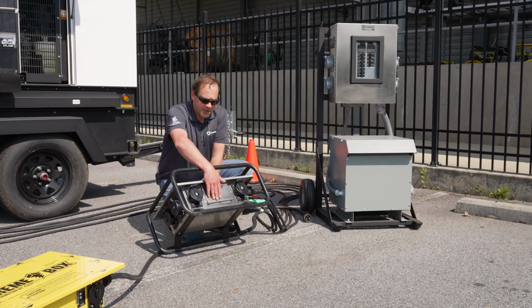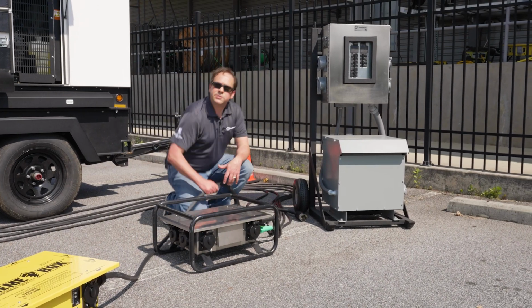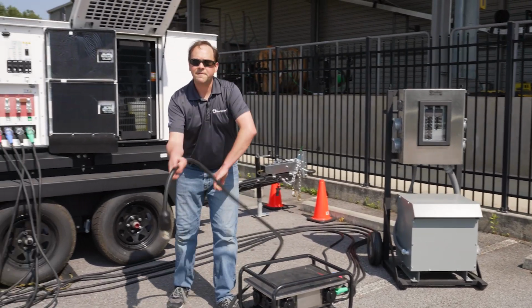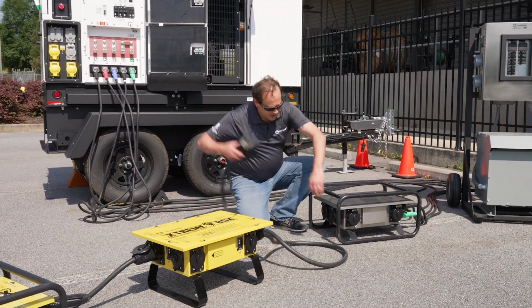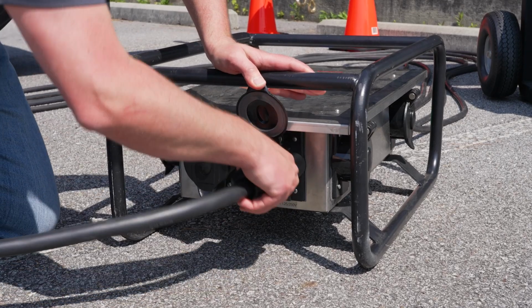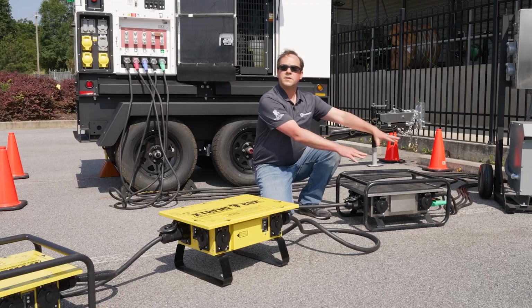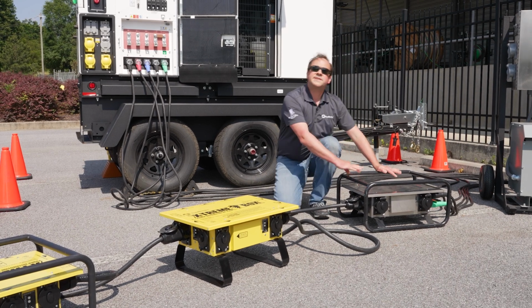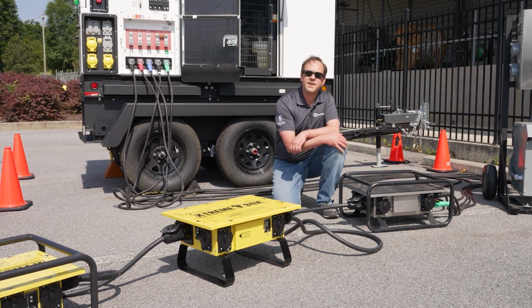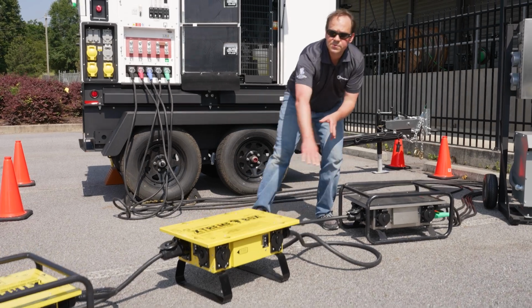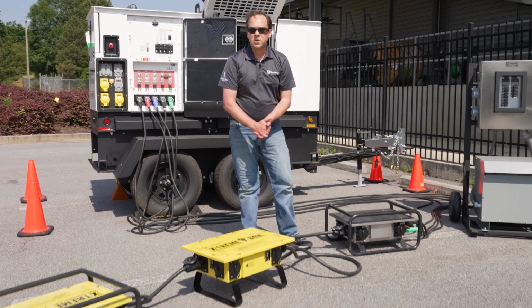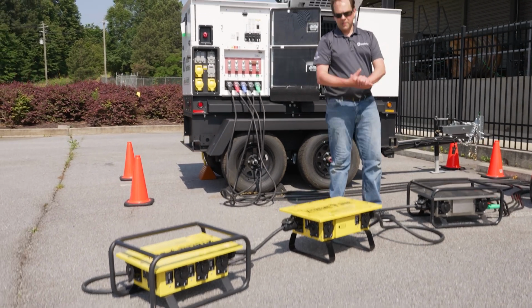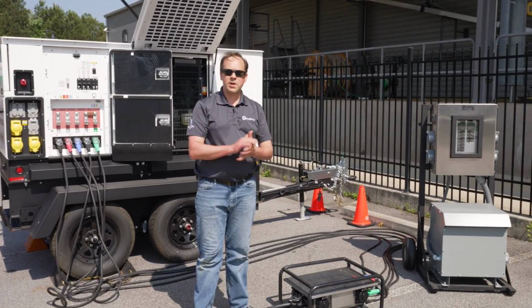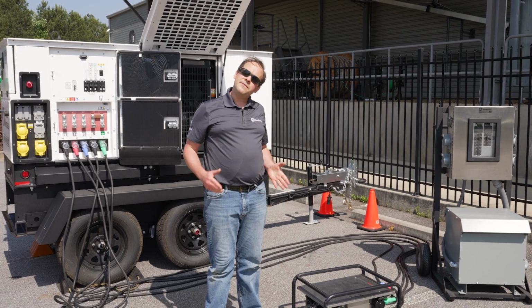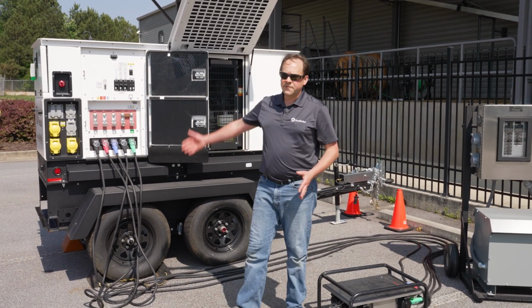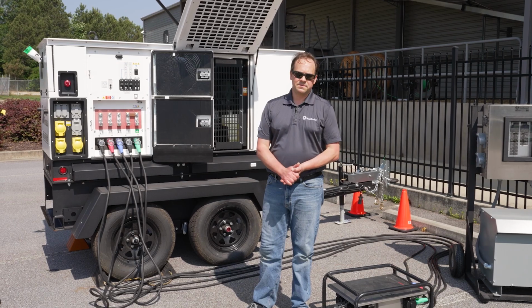Now, if you've watched our earlier videos, pretty much from here on, we're just going to connect our temporary power boxes. Here I have that 50 amp cable. I'm going to connect it to one of these 50 amp receptacles. Now, this 200 amp power distribution center is actually capable of up to 6 50 amp outputs. That means you could have 6 runs down to your temporary power boxes, all from the same device. Now, again, you want to make sure that you're staying within that 300-foot rule from your power source, or that you're having an electrician calculate voltage drop, as different size generators will output different amperages.